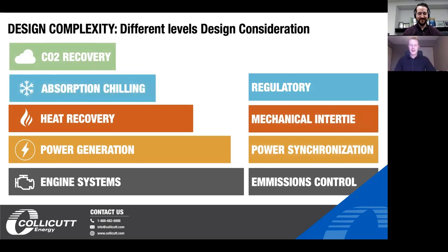One of the things I wanted to show here is that we typically start with CHP designed around the engine. Then from there we're going to determine the right power generation alternator. So what voltage is your building at? What's the right voltage to be operating? Are we 480, 600? Are we medium voltage? Are we 4160, 13.8? Are we lower or higher voltage than that?